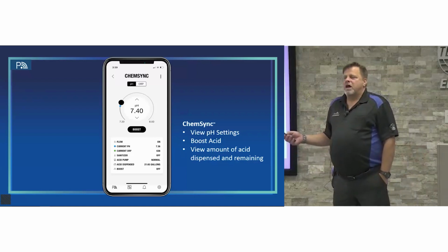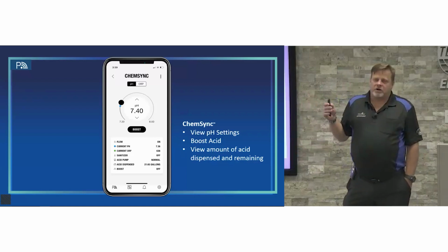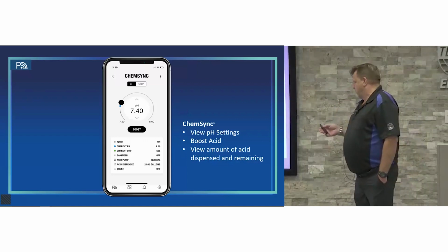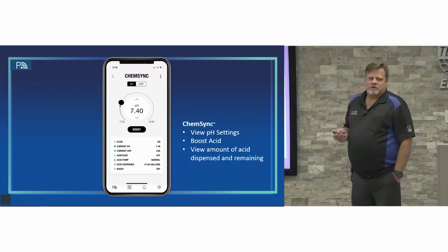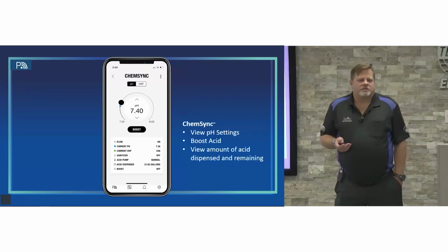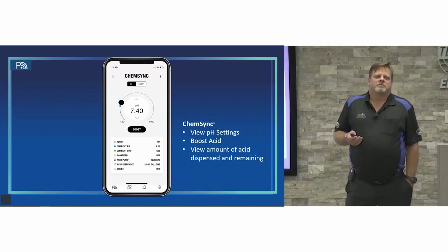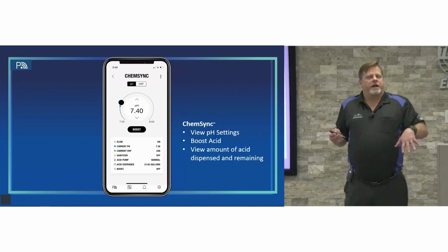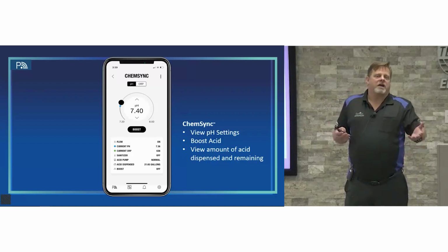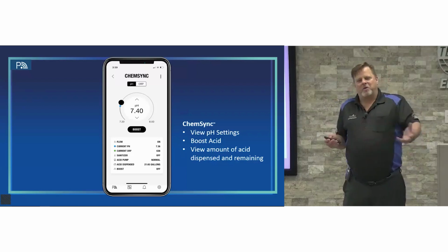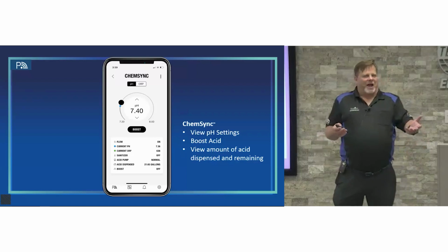Now, you notice there's pH calibration, but there is no ORP calibration. So what about if they take the reading in the middle of the day, when the sun is beating down on the pool water? Well, sunlight will affect the ORP reading based upon how much stabilizer you have in the water. It really shouldn't affect your actual parts per million reading, because the parts per million reading isn't affected by sunlight.